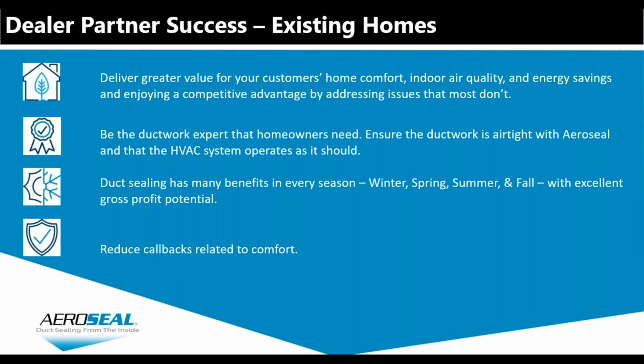So what that means is if ductwork is in wall cavities, the only way to get to it, to seal it, is to do some level of demolition, and that's just not realistic, right? So by using Aeroseal, it doesn't matter where the ducts are located, it doesn't matter what duct material, whether it's sheet metal, duct board, flex duct. In some cases, in slabs, there's clay duct material. So it doesn't matter what that is, they're able to go in and address it. So it's going to be solving the customer's comfort level for sure, but it gives a higher level of completion to the job. Next here, on being the ductwork expert that homeowners need, it's going to ensure that the ductwork is airtight and that the system is going to operate as it should.